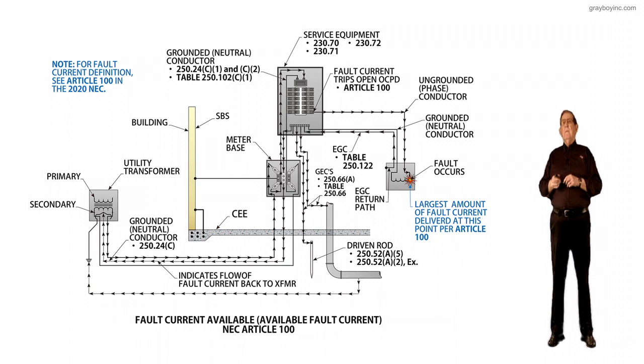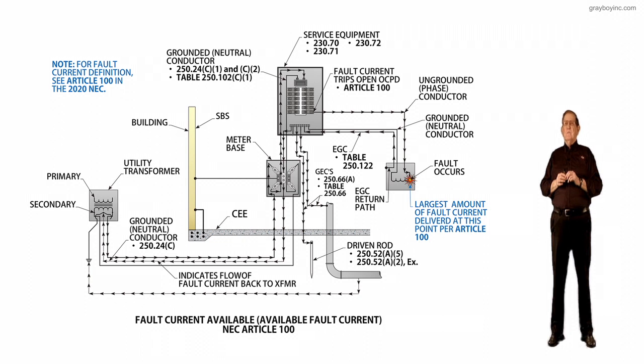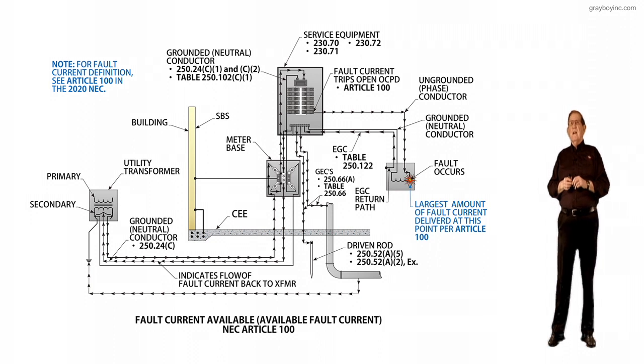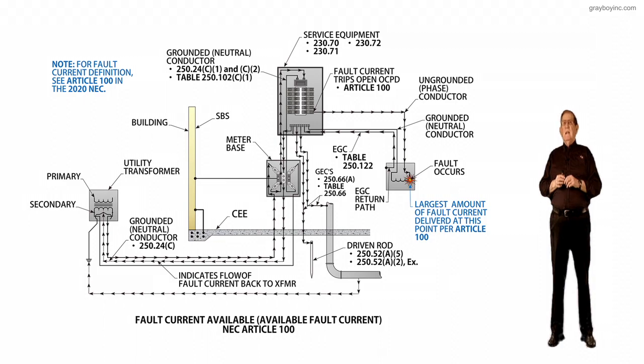chapter 17, those old circuit breakers may not clear in 8 to 9 cycles, and you think about that. That means that available short circuit current at that one point is going to take 9 cycles before it will ever clear. And basically 70E says take the cycles, if it was 9 cycles, multiply it by 0.0167, and that would give you the clearing time in seconds. So we like these circuit breakers to clear in about 2 cycles or less, and so we kind of comply with 70E and 70B.